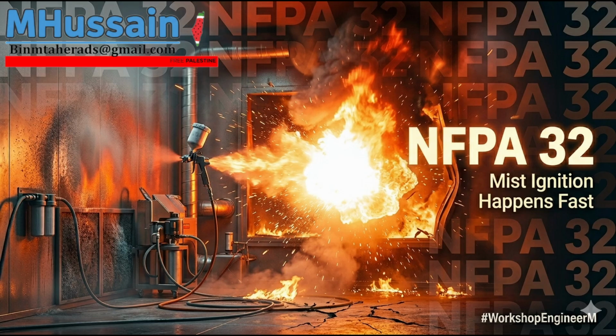The 2016 standard required the solvent manufacturer to certify the flash point and flammable limits of the solvent under the actual anticipated conditions of dry cleaning operations, not just in a sterile lab test. That certification is vital for the design engineer. A generic material safety data sheet just gives you parameters at standard temperature and pressure.